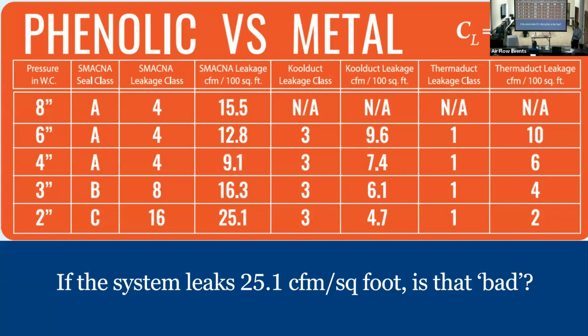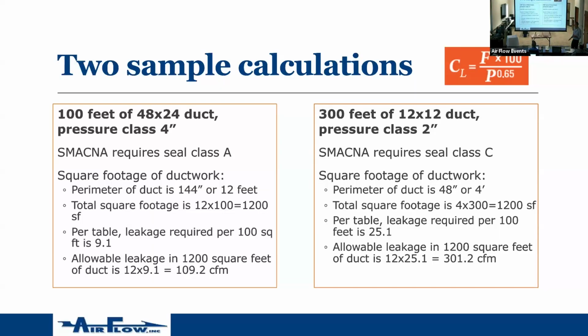I'm going to show you guys what Koolduct is. No matter how you build Koolduct, it's leakage class 3. That means the leakage drops to about 1/5 of what low pressure ductwork is. If you go to Thermaduct, which we'll talk about later, that's outdoor ducting, it barely leaks at all. But again, we're on the inside of the building right now. Quick math: 100 feet of 4x2 ductwork, a very common, not 10,000, but less than that, CFM air handler, you're allowed to leak 109.2 in that much ductwork. Ironically, in the same square footage of class C ductwork, you're allowed to leak 3 times as much.